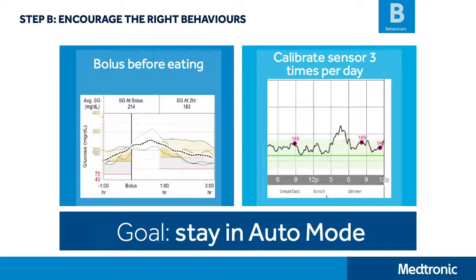before eating. The second key behavior is to calibrate the sensor 3 times a day on a schedule. The system only requires calibration every 12 hours after the first day. However, the accuracy is improved with 3 calibrations per day. Additionally, we want to make sure that the patient calibrates before bed so that he or she is not asked to calibrate overnight. If the patient adopts these behaviors, bolusing 15 minutes before eating and calibrating 3 times a day on a schedule, the patient will spend more time in auto mode.